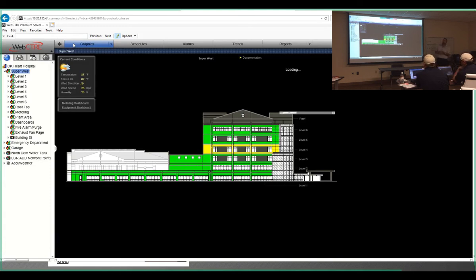One thing we did with these air handling units: we're controlling all the air handling units down to the pressure on the floors. But we were worried about building up too much static up at the top of the air handling units. So if we lost communication on what's down on the second floor with air handling unit 2, air handling unit 2 automatically defaults and will start running that static pressure sensor that's up in the unit.